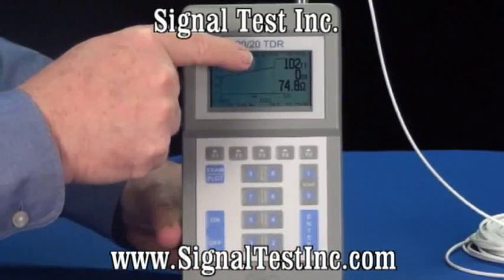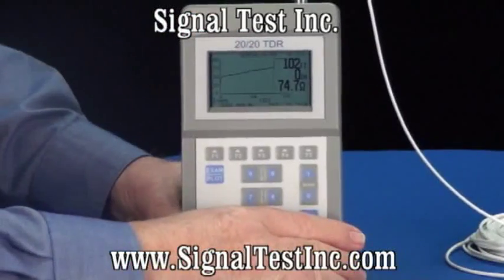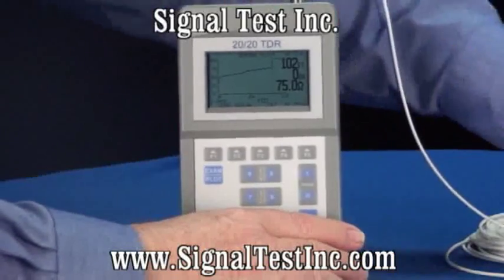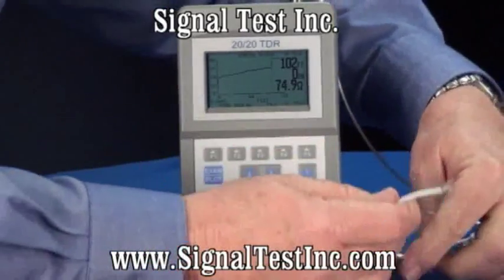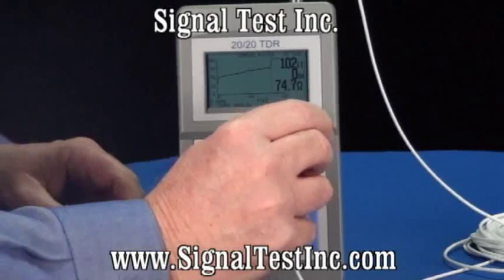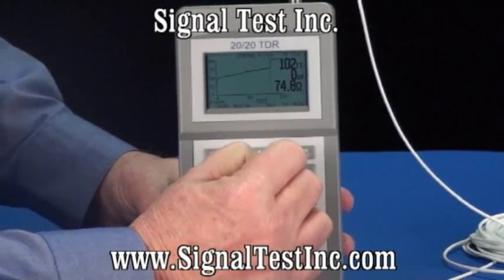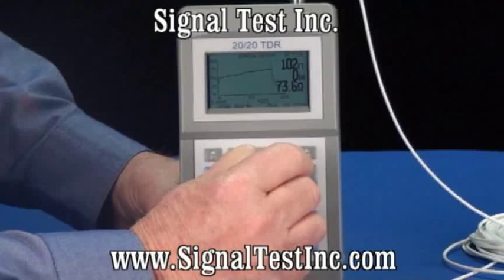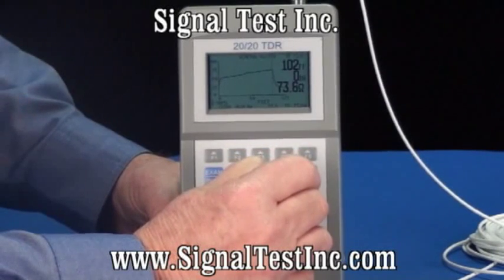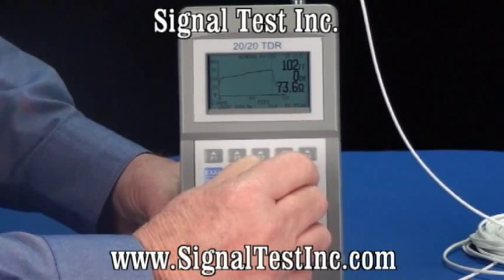The open is demonstrated by a sharp upward deviation in the impedance trace, and if I were to short the end of the cable, as I'm doing here, you will see the trace goes down to 0 ohms at the bottom, or a sharp downward turn in the trace.